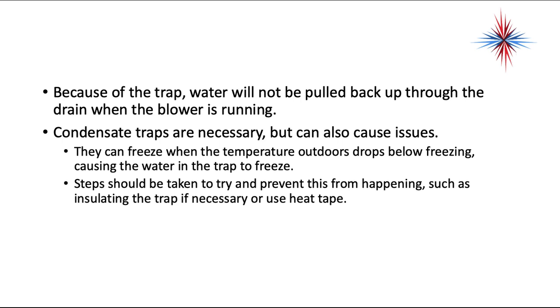Condensate traps are necessary but can also cause issues. They can freeze when the temperatures outdoors drop below freezing, causing water in the trap to freeze. You want to try to prevent this from happening, such as by insulating the trap if necessary, using heat tape. Again, if you're in a cold environment and the air conditioning is never going to run in the winter months, you really don't have to worry about this as badly.